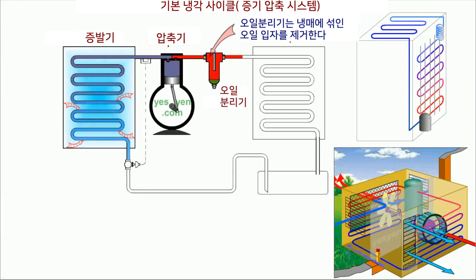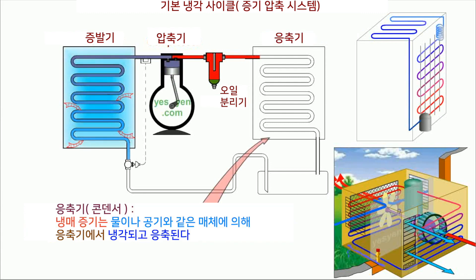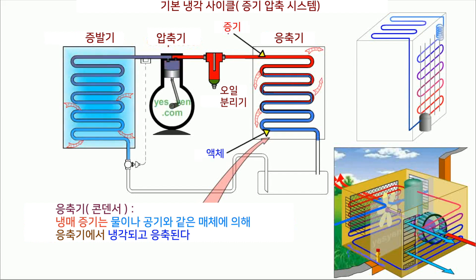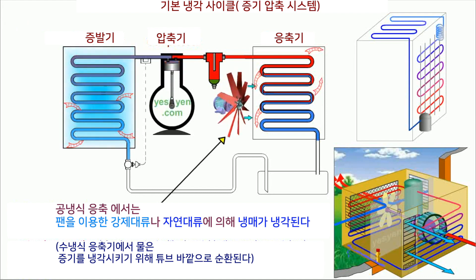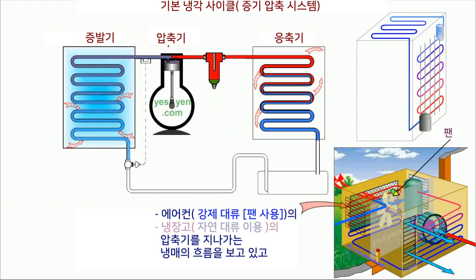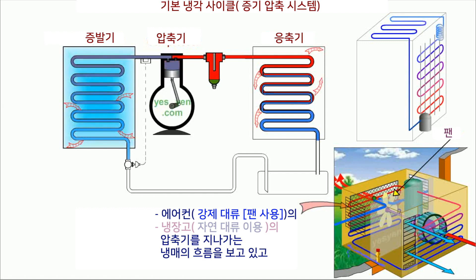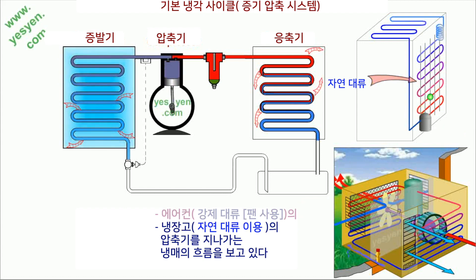Suspended oil particles are removed from the refrigerant in the oil separator. Condenser: Refrigerant vapor is cooled and condensed in the condenser by a cooling medium like water or air. In air-cooled condensers, the refrigerant is cooled by forced convection using fans, or by natural convection. In water-cooled condensers, water is circulated outside the tubes to cool the vapor. The flow path across the condenser in the air conditioner using forced convection and in the refrigerator using natural convection is depicted.